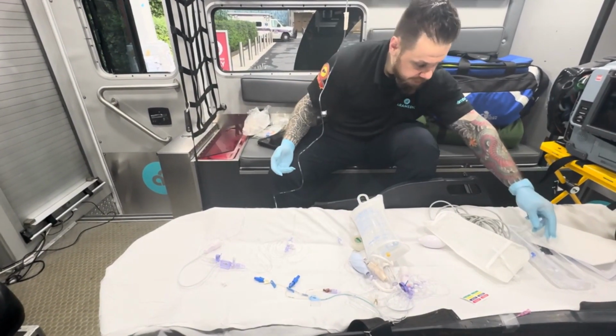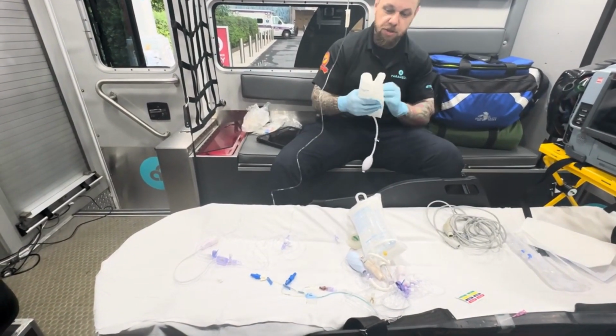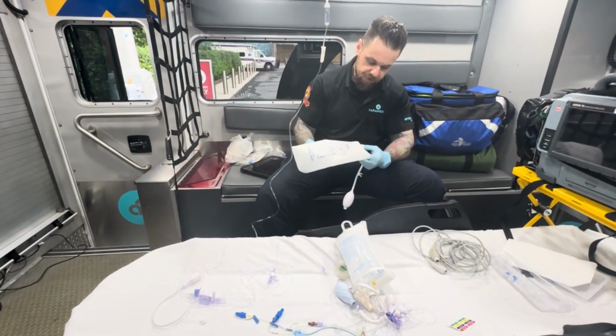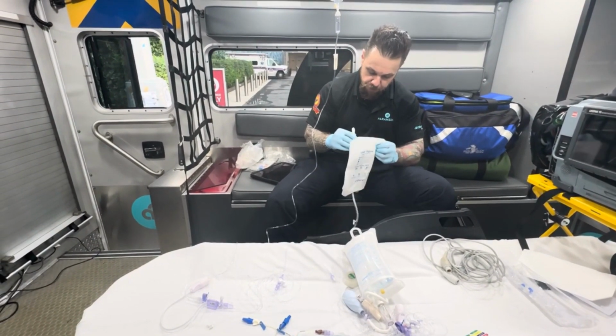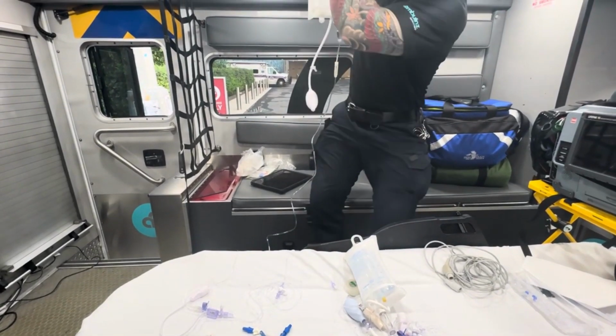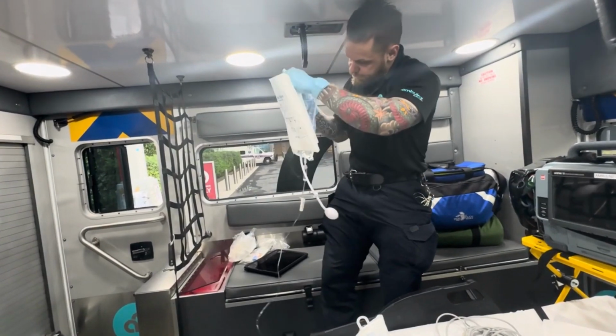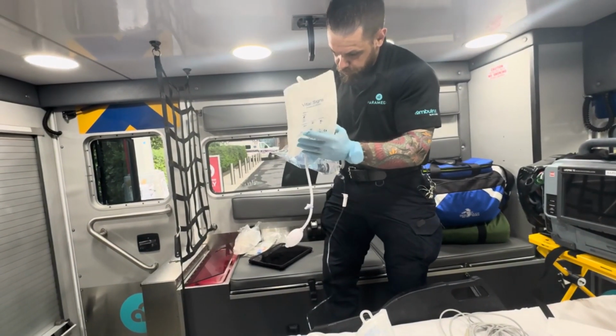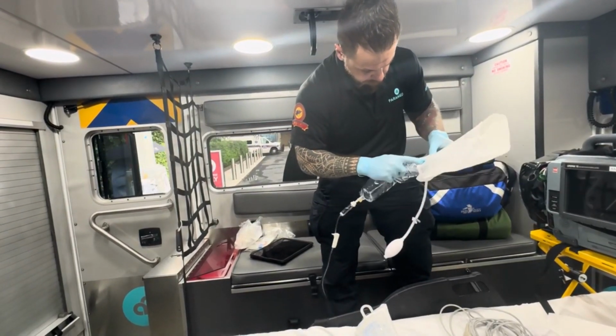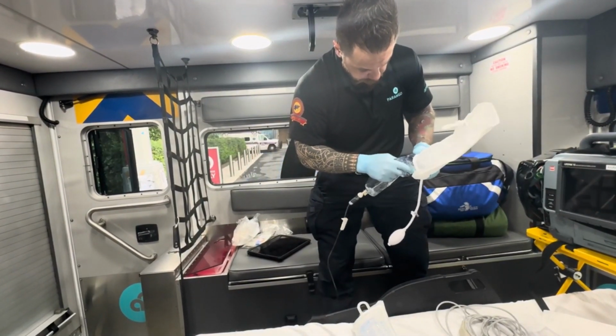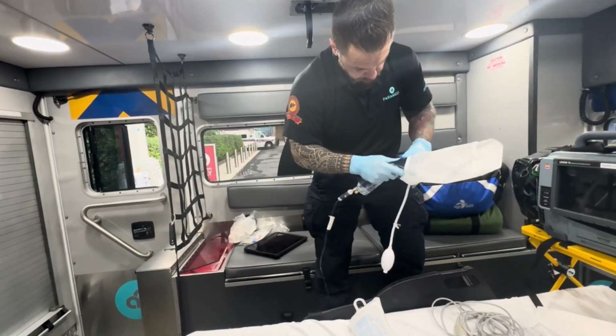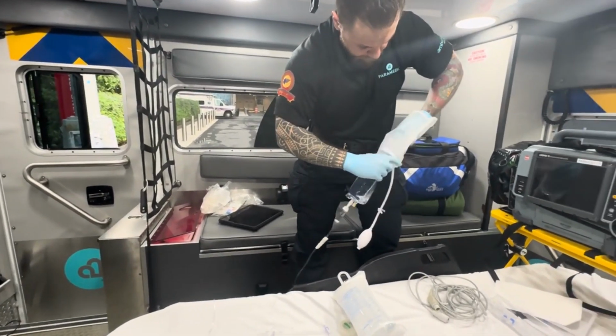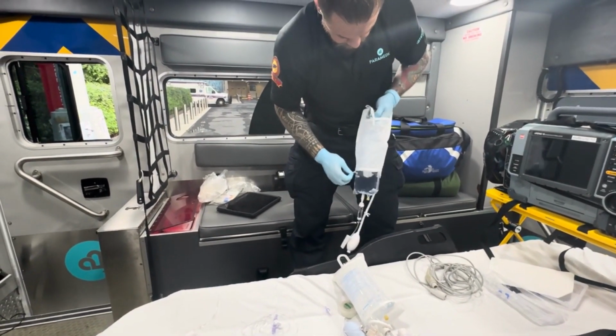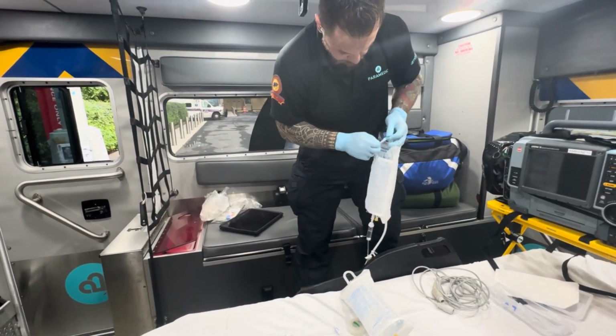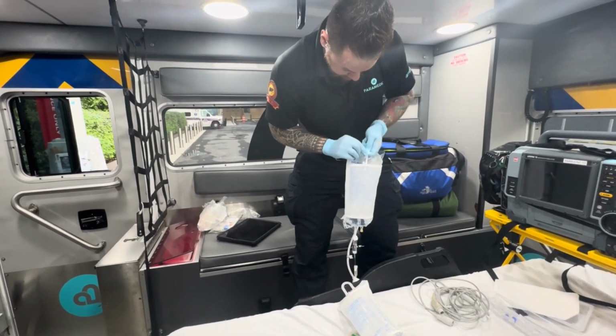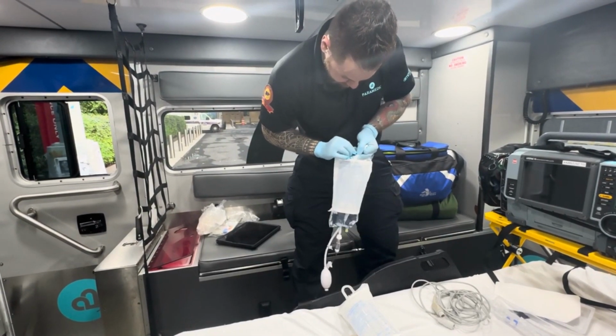The next thing that I like to do is, this is the part that we have to pressurize. So this is where the manufacturer says you're going to pressurize your fluid. Once again, this bag is not rated for it, but I'm going to put it right in here so I can show you what 300 looks like. But you use the appropriate size bag for your fluids. So it will be essentially placed under here. Grab it at the top and then you slide it across. This portion goes under here and your bag will rest like so.